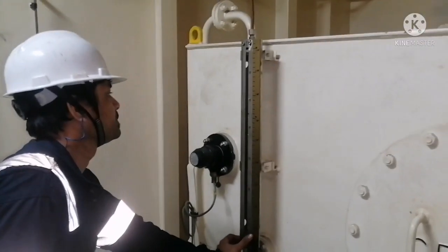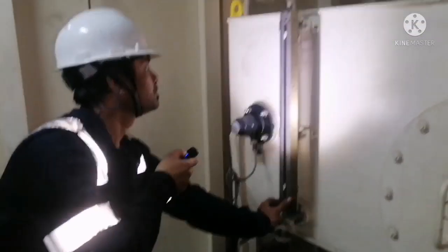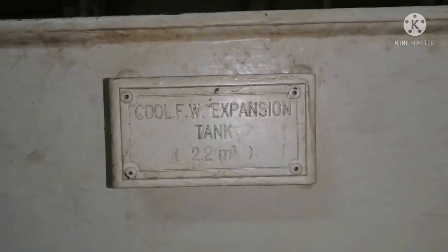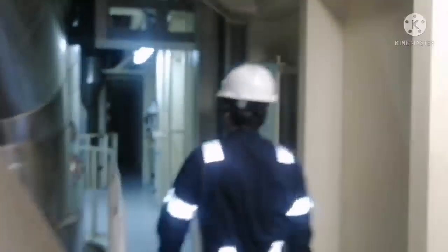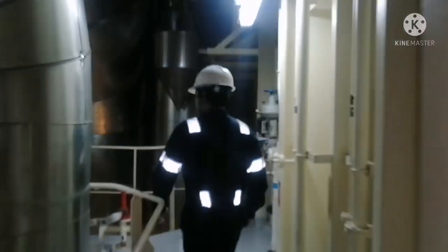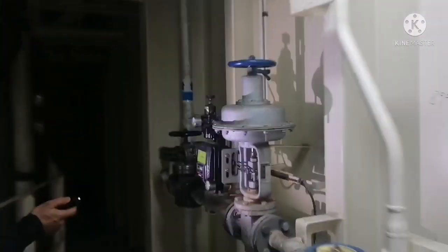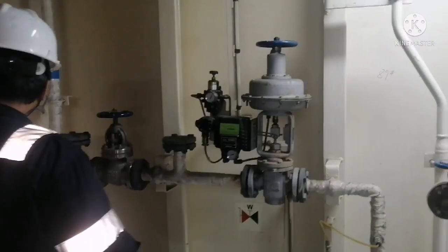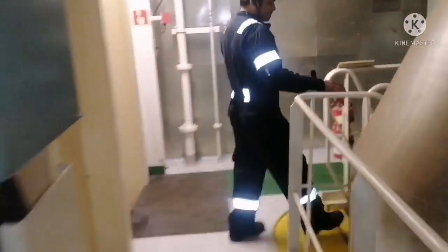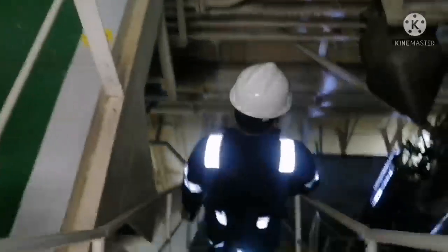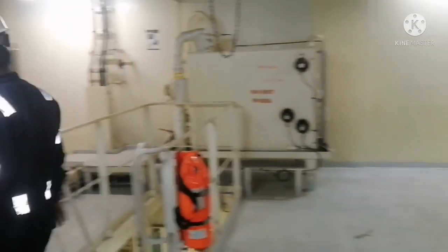Next platform, it's a freshwater expansion tank. So you have to check the level in the freshwater expansion tank. If the level is low, you have to top it up to the required level. So we just have a look on that platform, have a round, check for any abnormality, any leakage, anything. So just take a look on top of the platform, pipelines and everything. Just check visually whether there are any leakages or something. And okay, on this platform there are no leakages, and round done. And I am getting down to the next platform.